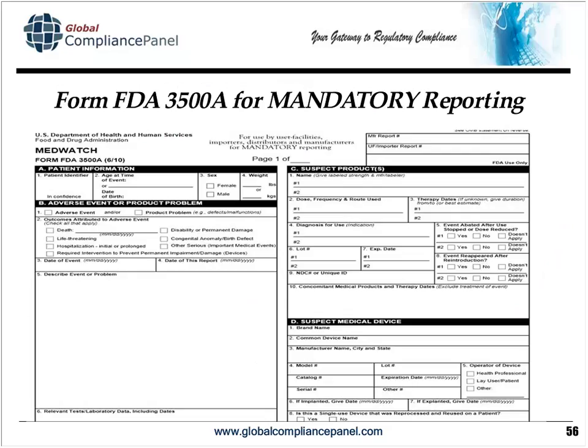Now, this is the FDA mandatory reporting form. Here's the manufacturer report number. Please note, here are the A, B, C, D. You can call it Section A or Block A. Both terms are used interchangeably, but for today's webinar, let's use Section A. For example, Section A, patient information. Under Section A, there is a number 1, Section A1, patient identifier. Below it says in confidence. That means you don't give the actual name of the patient. You do not provide the patient's social security number. You provide just any coding system that can identify the patient, not the social security number, not the actual name.